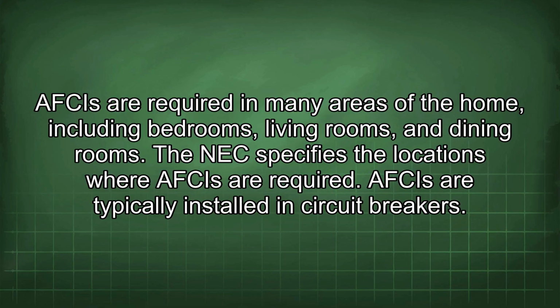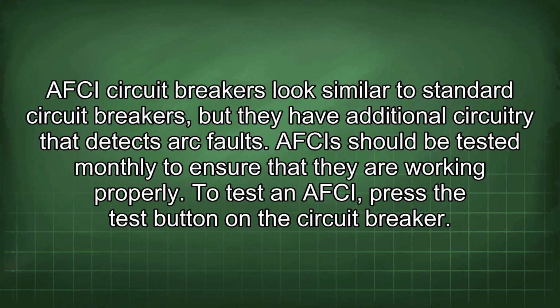AFCIs are required in many areas of the home, including bedrooms, living rooms, and dining rooms. The NEC specifies the locations where AFCIs are required. AFCIs are typically installed in circuit breakers. AFCI circuit breakers look similar to standard circuit breakers, but they have additional circuitry that detects arc faults.